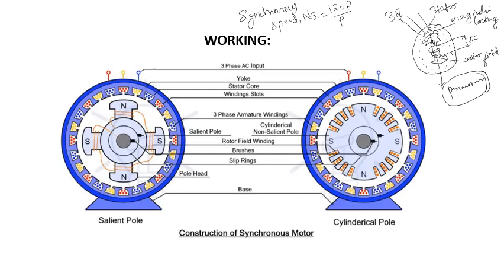To make the motor self-starting, we provide some external support. If we provide a prime mover to the rotor and make it rotate, when the motor attains a particular speed, at a particular instant, the opposite poles of both magnetic fields get locked and the rotor starts to rotate at synchronous speed. The working principle of a synchronous motor is the interaction of stator and rotor magnetic fields, or in other words, the magnetic locking of the stator and rotor magnetic fields creates the rotating movement.